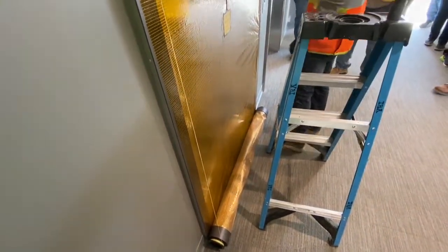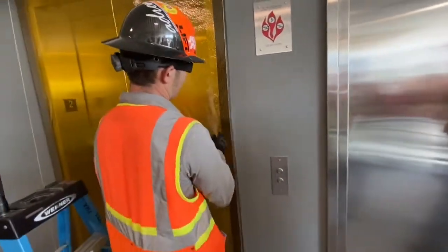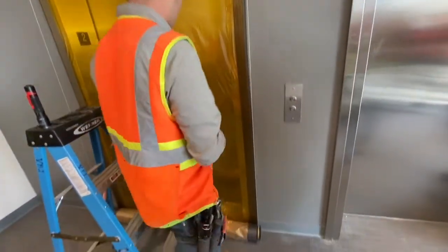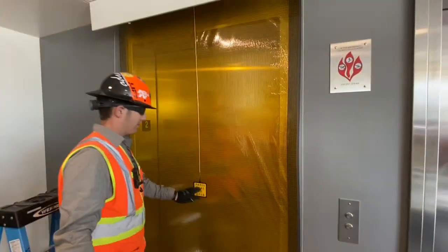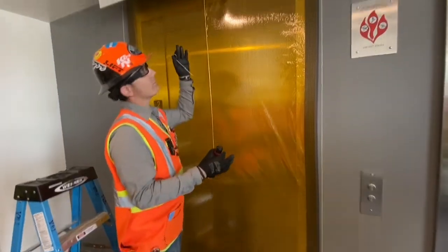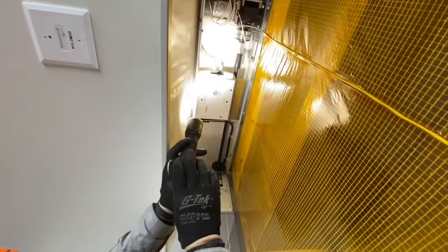These things are very easy — all magnetic. This is the rail retract. So even if the thing gets crooked, you can always just line it back up and put it back on. And then in the event of the fire alarm, you hit that button and it rolls itself back up. But since it's in testing right now, all I really did was turn it off. And if you look up here, there's that on and off switch.